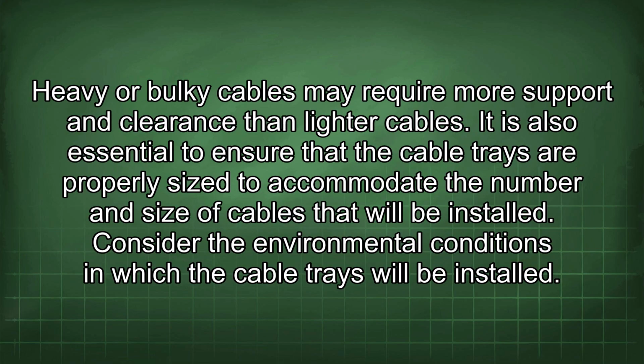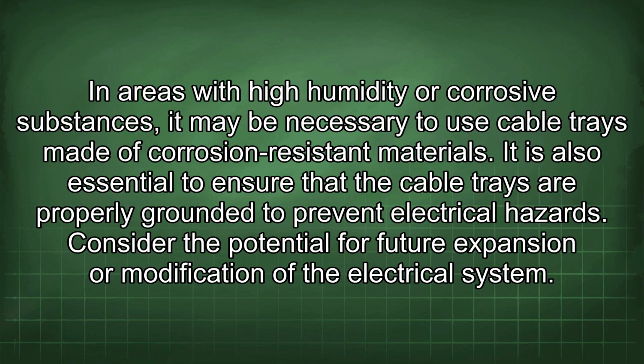Consider the types of cables that will be run in the cable trays. Heavy or bulky cables may require more support and clearance than lighter cables. It is also essential to ensure that the cable trays are properly sized to accommodate the number and size of cables that will be installed. Consider the environmental conditions in which the cable trays will be installed. In areas with high humidity or corrosive substances, it may be necessary to use cable trays made of corrosion-resistant materials. It is also essential to ensure that the cable trays are properly grounded to prevent electrical hazards.